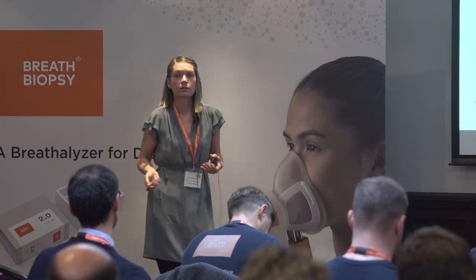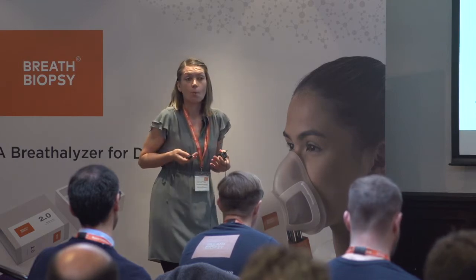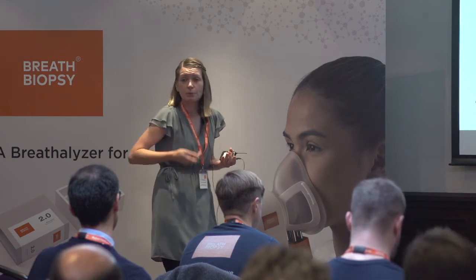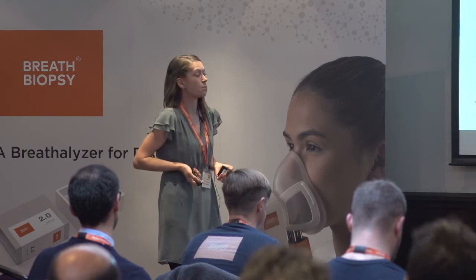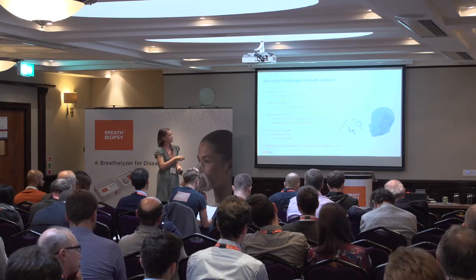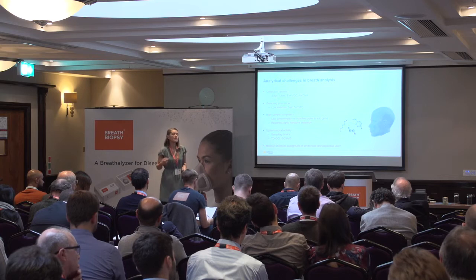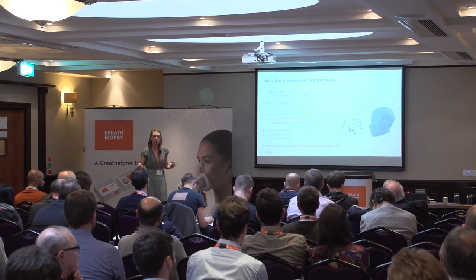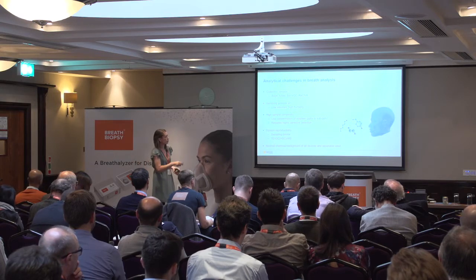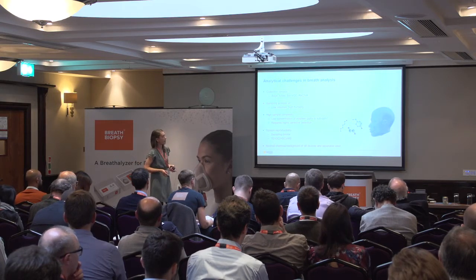But you've also got to remember the rest of the analytical system as well, and ensure that you're not looking at compounds that are from consumables and introduced within the system itself rather than from the breath sample. So you have to ensure that there's minimal chemical background on all parts of the equipment, from consumables all the way through the TD, GC, and MS.